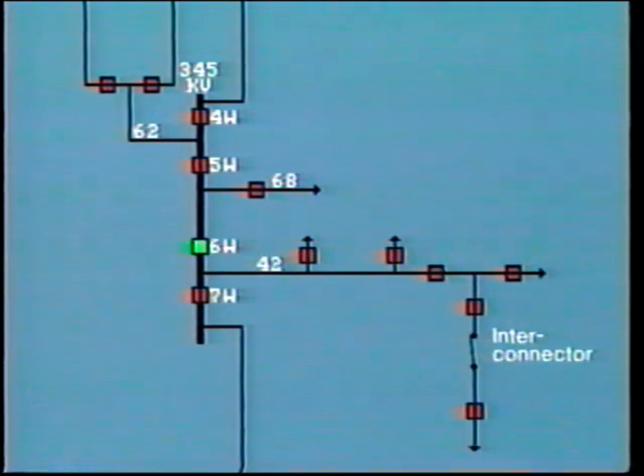In this installation, a lightning arrestor failed, resulting in a ground on one phase of the 345 kV bus. Note that at the time this bus section breaker 6W was open, with the station operating as a split bus. Under this configuration, we would expect the bus fault to trip breaker 5W on the faulted side of the bus. This is in fact what happened, thus isolating line 68. However, breaker 4W also opened, isolating transmission line number 62. This trip was not correct.